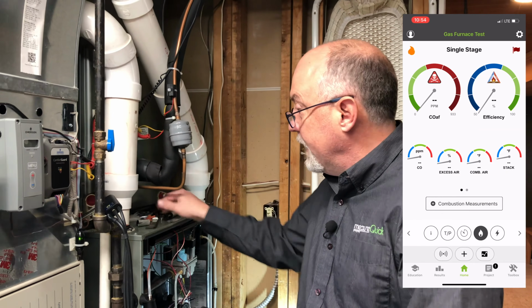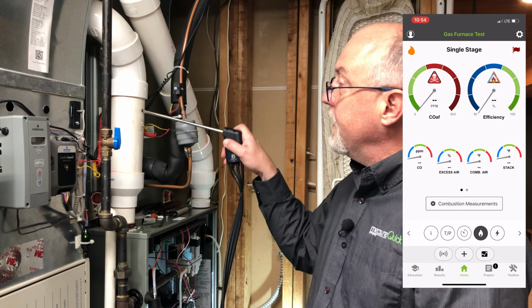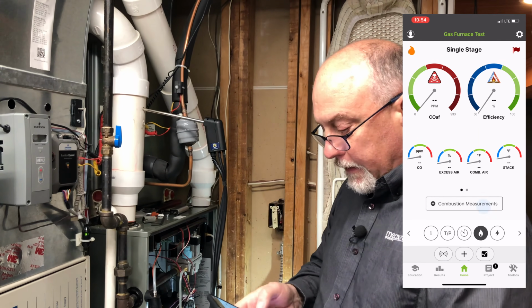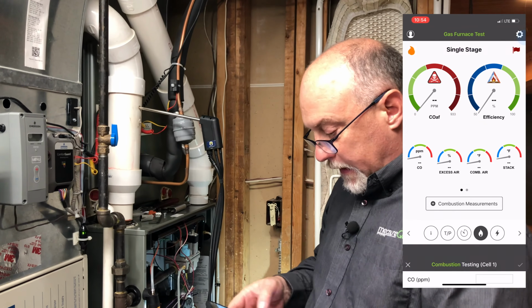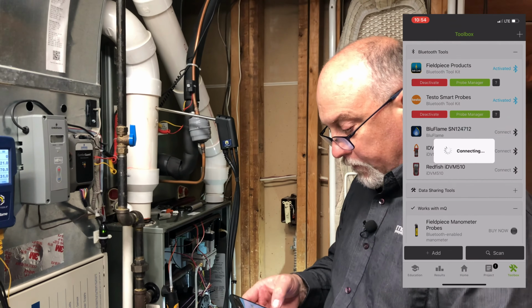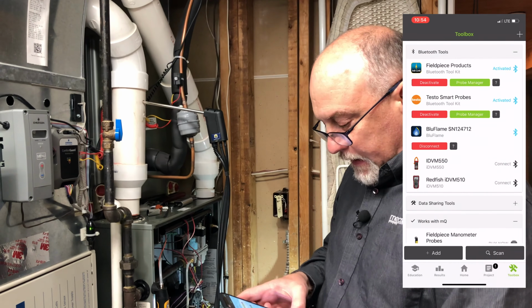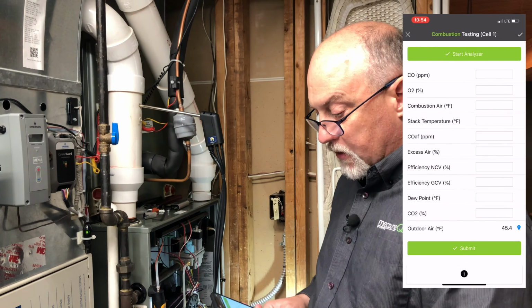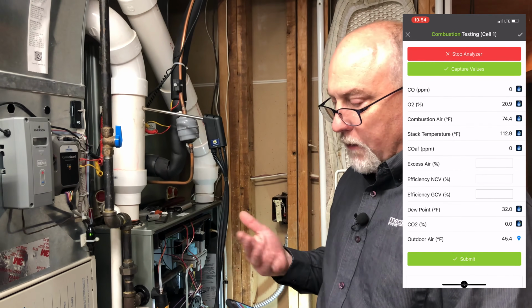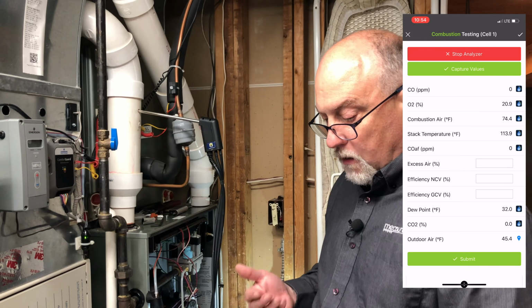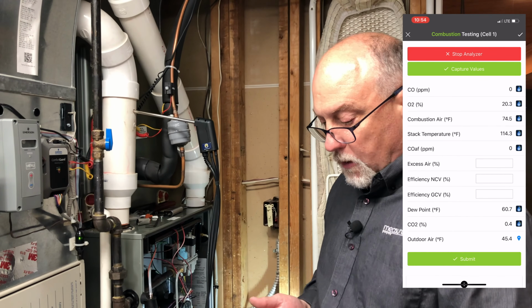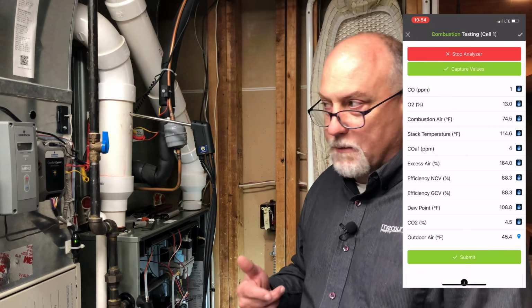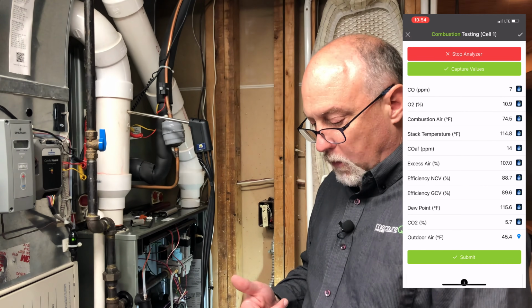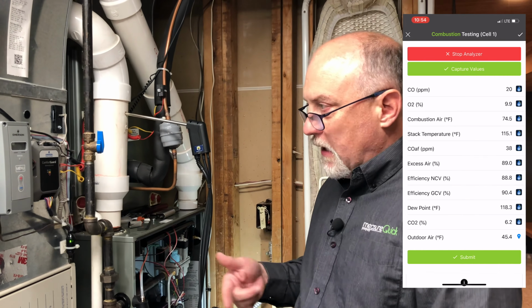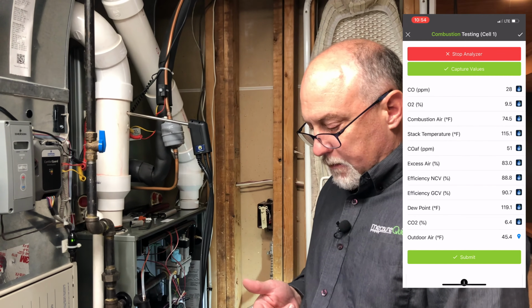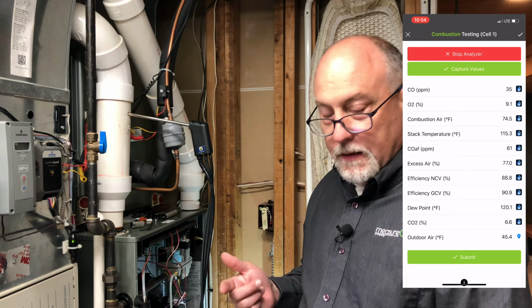So again, I'm going to go back in here, put my probe in the stack, touch the back, pull it back about halfway, go to combustion measurements, and I do have to go in and connect my analyzer because I lost connection out there. So just go in the app and reconnect it, home, combustion measurements, and we'll start the analyzer. So now this is going to pull all the readings in from the analyzer, and we're going to look at our CO, O2, combustion air, stack temp, CO air free. You'll notice some readings don't calculate right away, and that's because the analyzer has to get it into range before they start calculating. And we really just got to let this run for a few minutes until our stack temperature stabilizes, and that's a really good indication that things are there.